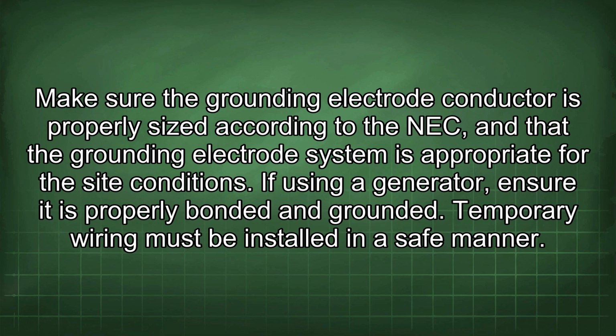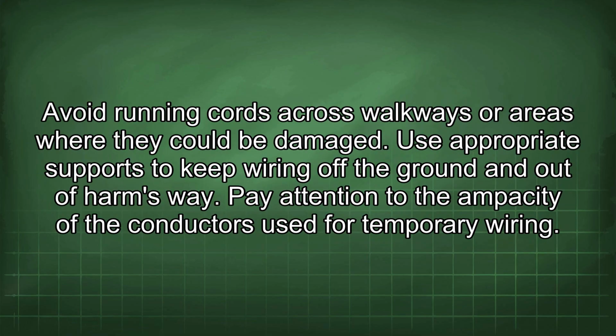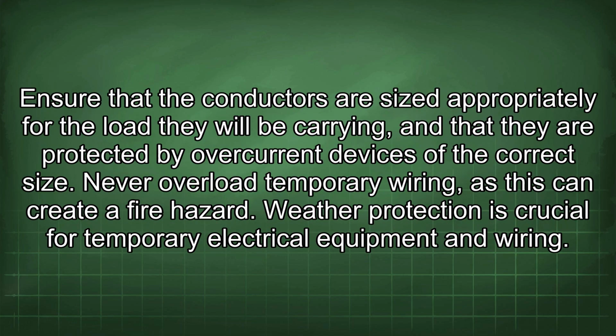If using a generator, ensure it is properly bonded and grounded. Temporary wiring must be installed in a safe manner. Avoid running cords across walkways or areas where they could be damaged. Use appropriate supports to keep wiring off the ground and out of harm's way. Pay attention to the ampacity of the conductors used for temporary wiring.